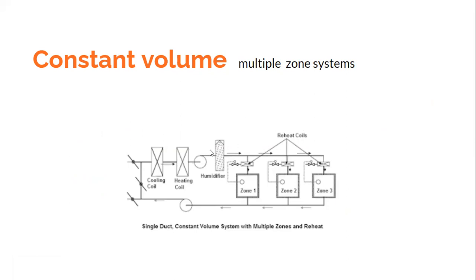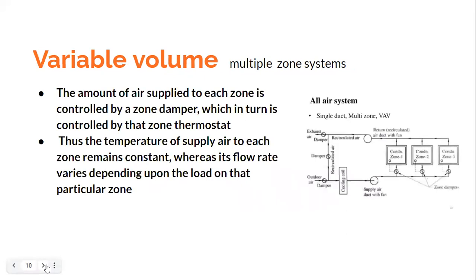Your volumes are the same, so you find that the same condition is being supplied to the 3 zones, but still you are maintaining different conditions in zone 1, zone 2, zone 3 by using these zone thermostats. These zone thermostats give the inputs to the reheat coil, and accordingly we can control the water which is circulated in the reheat coil or the supply of electricity to the reheat coil to adjust the temperatures in the different zones. Okay, so this is single duct. As you see, there is a single duct, a constant volume system. The volume is constant, but there are multiple zones because the temperatures are maintained at different levels, and it is employing reheat, a reheat coil, to achieve this.